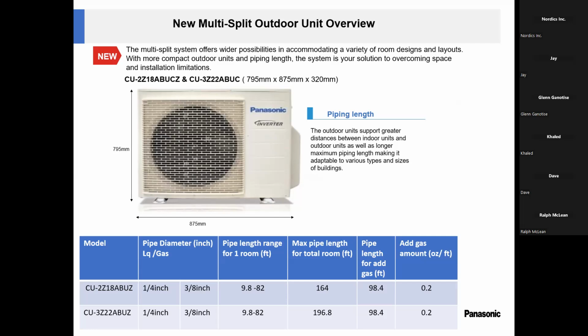And for the 3-zone, same pipe size like before, like the older units. If you had done our older multi-zone, I hope you had used 3/8 and 1/4 and not based on the size of the indoor unit. Okay, you should not be piping these units based on the size of the indoor units. You will be piping them based on the size of the outdoor unit. Okay, and then when you get to the indoor unit, use an adapter for the 12,000, for the 18,000, 15,000, and obviously 24,000.